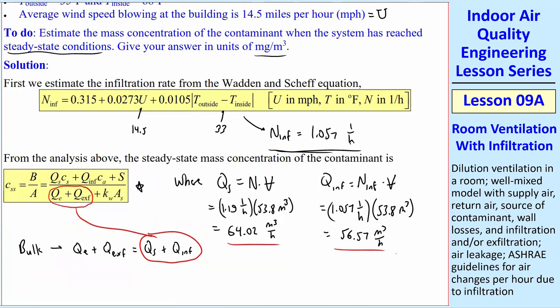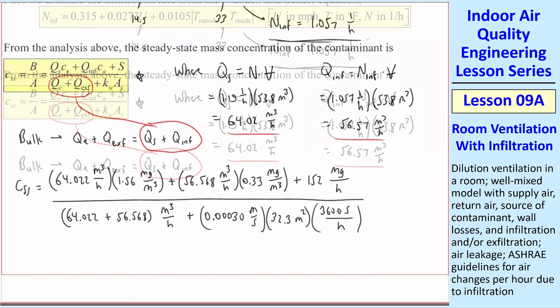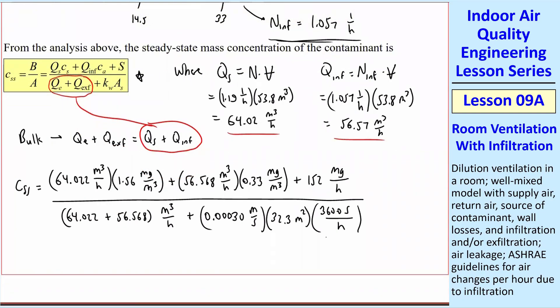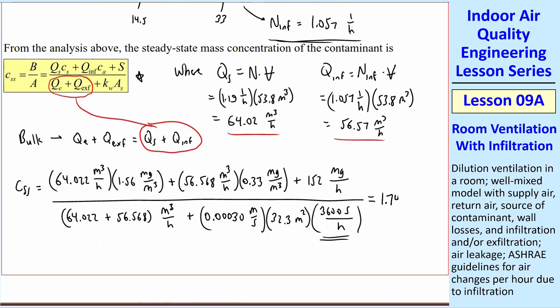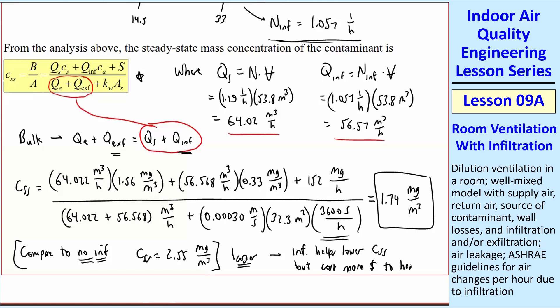So now we're going to plug in everything into that equation to get our final answer. So I threw in all the numbers. The only unit conversion I need is right here, 3600 seconds per hour. And I get 1.74 milligram per meter cubed compared to the case with no infiltration. Let Q_INF equals zero here and Q_EXF equals zero. And I got C_SS is equal to 2.55 milligram per meter cubed, which of course is bigger. Infiltration helps to lower C_SS, but it will cost more dollars to heat in this case.